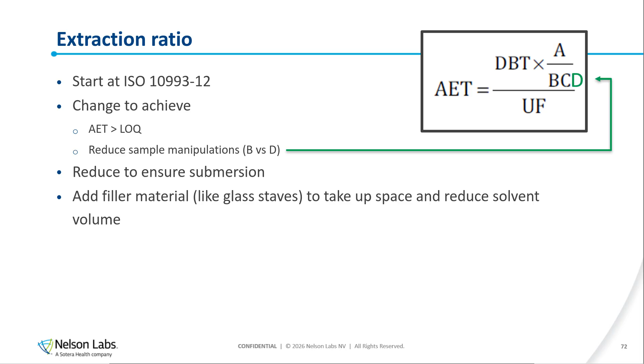Now, to show this in the same example, we have the same calculation, and I kept a concentration factor of 10. You see this as 0.1 in green. And we have a total surface area, once again, of 150 centimeters squared per device. If we would use an extraction ratio of 1 squared centimeter per milliliter, we would have 150 milliliters. It's just dividing your total surface area by the extraction ratio. And again, you can see we come to an AET that's below the LOD once again. That is not good. So let's increase our extraction ratio.